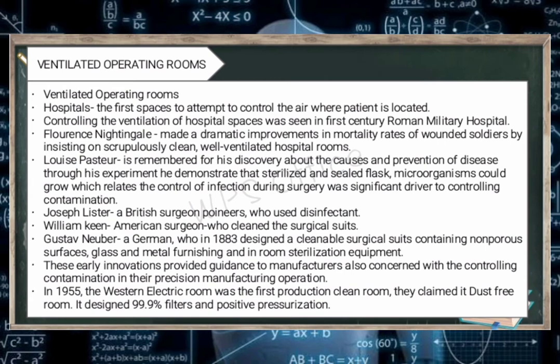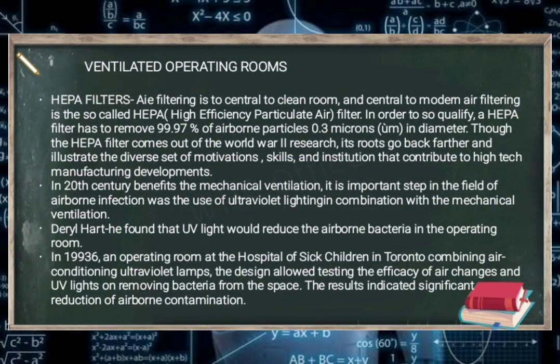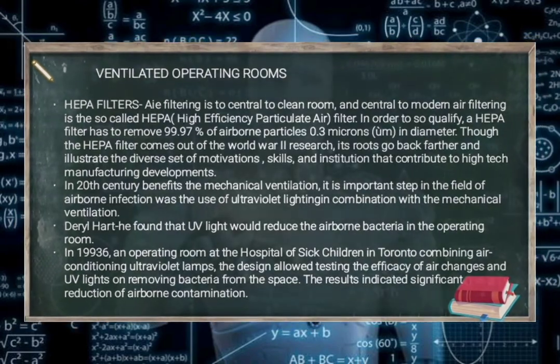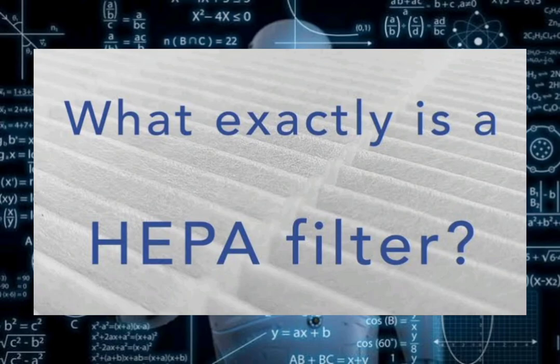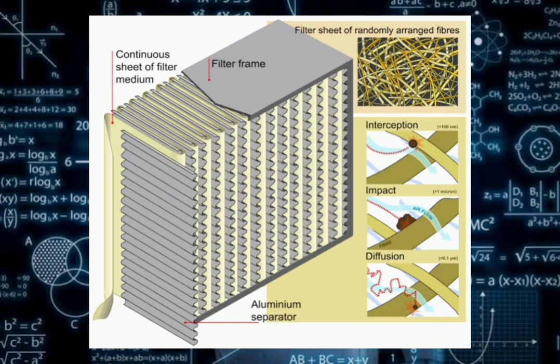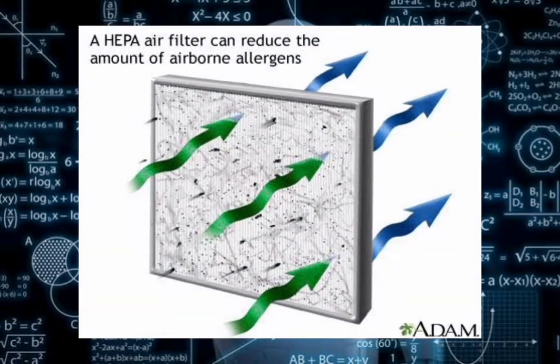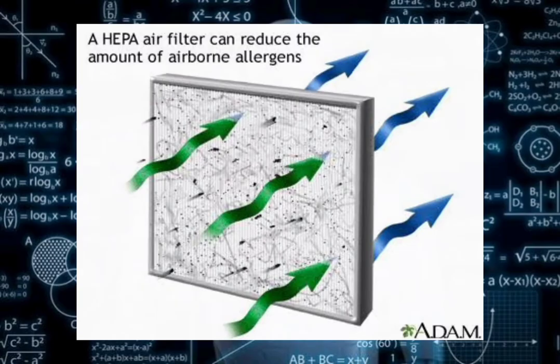In 1955, the Western Electric room was the first production cleanroom. They claimed it was a dust-free room. It used 99.9% filters and positive pressurization. HEPA filters—air filtering is central to cleanrooms, and central to modern air filtering is the so-called HEPA, High-Efficiency Particulate Air filter. In order to qualify, a HEPA filter has to remove 99.97% of airborne particles 0.3 microns in diameter. The HEPA filter comes out of World War II research. Its roots illustrate the diverse set of motivations, skills, and institutions that contribute to high-tech manufacturing developments.